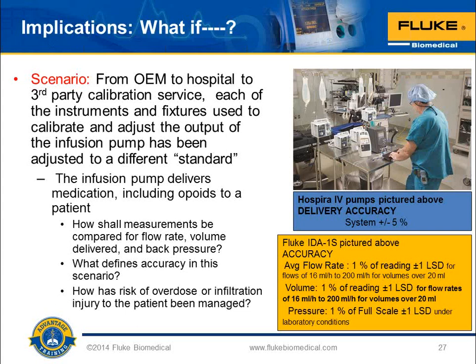Well, let's get it down to practical terms, why don't we? Let's do a little what if. Here's the scenario. From a medical device manufacturer, an OEM, to the hospital, to a third-party calibration service, each of the instruments and fixtures used to calibrate and adjust the output of an infusion pump has been adjusted to a different standard. The infusion pump delivers medication, including opioids, to the patient, or, for example, chemotherapy to the patient.